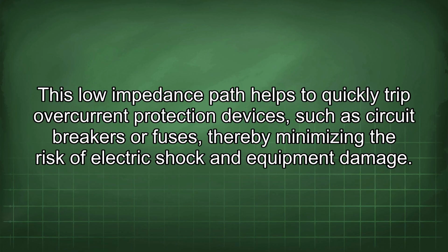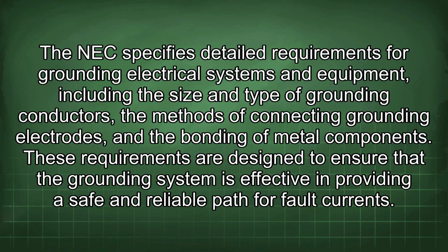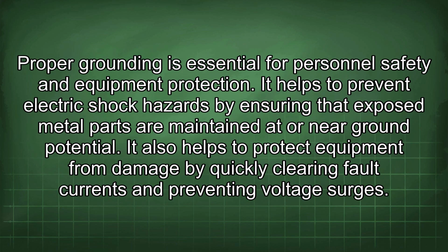This low impedance path helps to quickly trip overcurrent protection devices, such as circuit breakers or fuses, thereby minimizing the risk of electric shock and equipment damage. The NEC specifies detailed requirements for grounding electrical systems and equipment, including the size and type of grounding conductors, the methods of connecting grounding electrodes, and the bonding of metal components. These requirements are designed to ensure that the grounding system is effective in providing a safe and reliable path for fault currents. Proper grounding is essential for personnel safety and equipment protection.